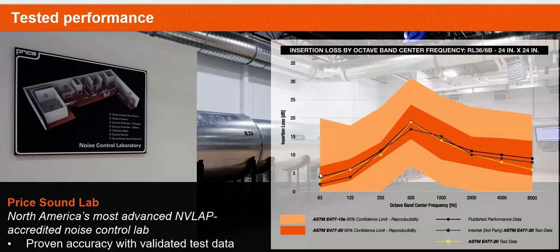So the takeaway on this slide for you is just to specify under the right standard would ensure that massaging on performance doesn't occur. So when you look at the limits on their ASTM E477, which is the dark orange, manufacturers cannot modify performance more than a couple decibels, which lines up with human sensitivity to pressure changes. A change in performance that was 1 to 3 decibels is not going to be sensed by the human ear. Any manipulation of performance that's larger than that could result in louder sound pressure levels in the space, especially if you're trying to treat heavy equipment. If all of a sudden your silencer doesn't do what it told you it was going to do, you could have some liability on the solution.